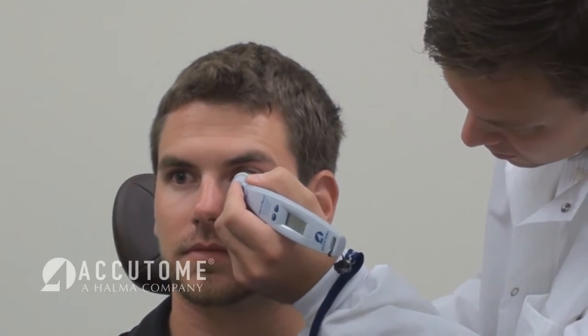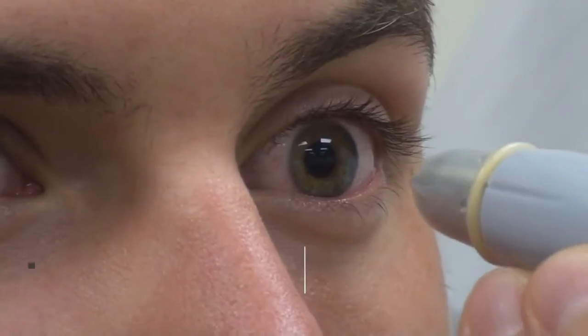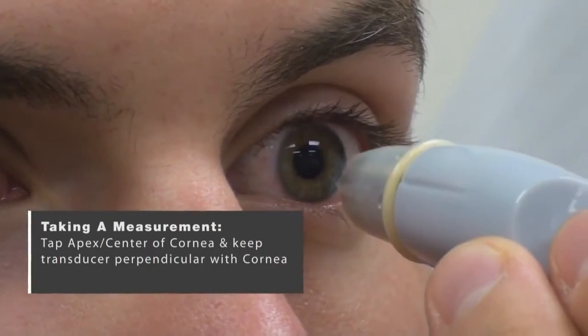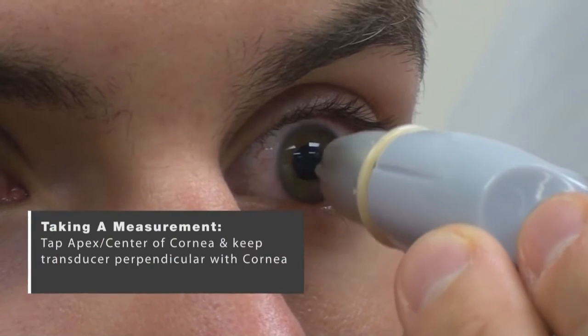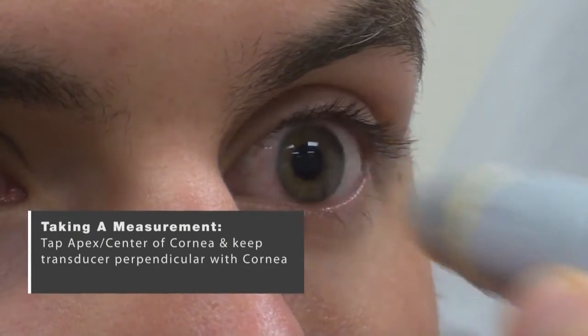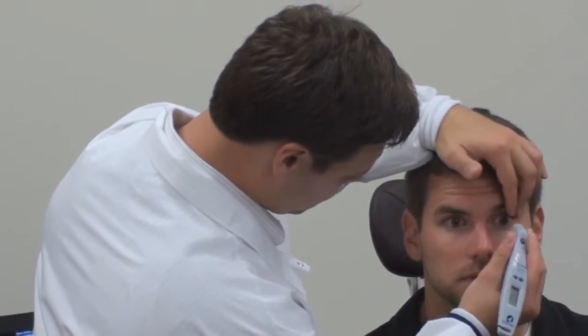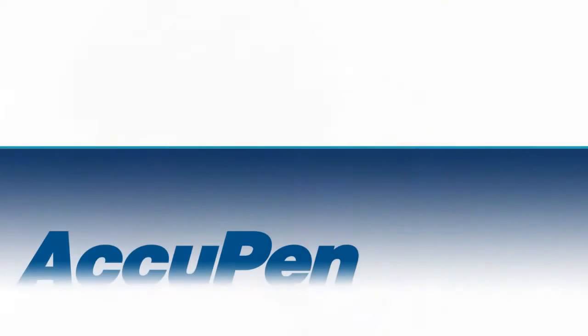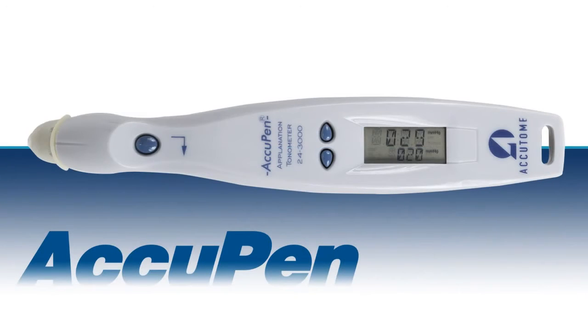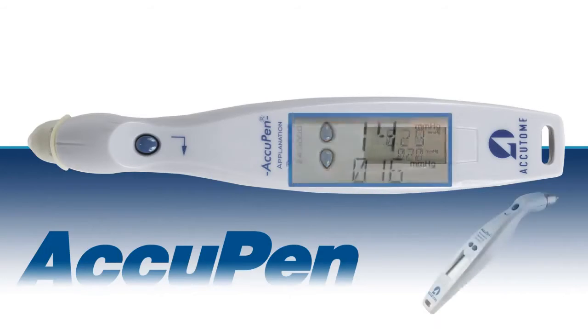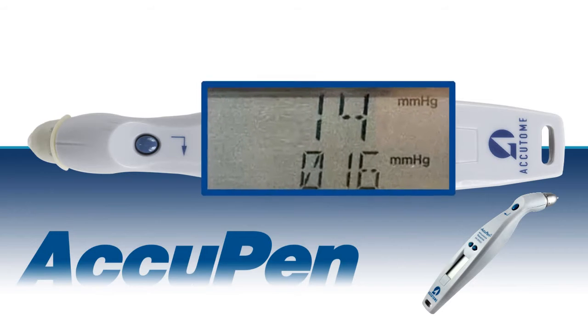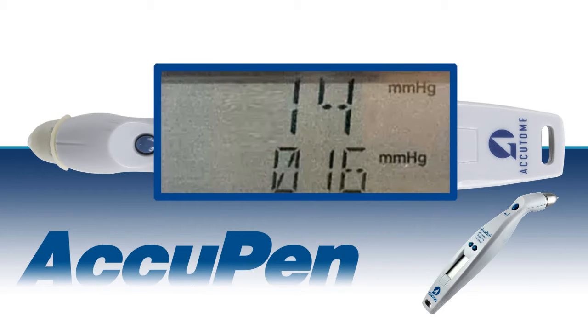Gently tap the transducer tip on the patient's cornea. The probe should be perpendicular to the apex of the cornea, and measurements should be taken at the center of the cornea. When the unit is being properly applanated to the cornea, the unit will produce short chirps followed by one longer chirp. The longer chirp indicates you have obtained an IOP measurement. The number of short chirps can vary, but typically 3 to 5 chirps will produce one measurement.